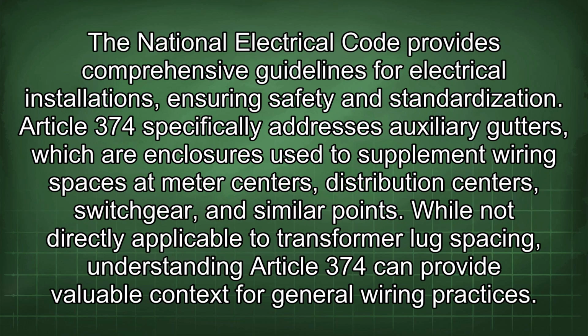The National Electrical Code provides comprehensive guidelines for electrical installations, ensuring safety and standardization. Article 374 specifically addresses auxiliary gutters, which are enclosures used to supplement wiring spaces at meter centers, distribution centers, switchgear, and similar points. While not directly applicable to transformer lug spacing, understanding Article 374 can provide valuable context for general wiring practices.